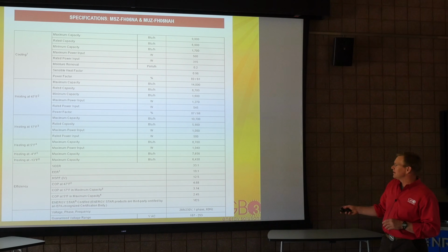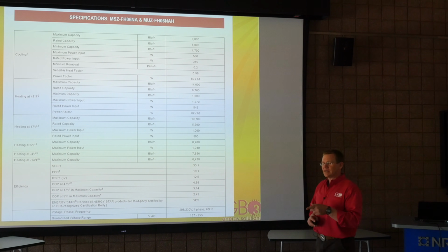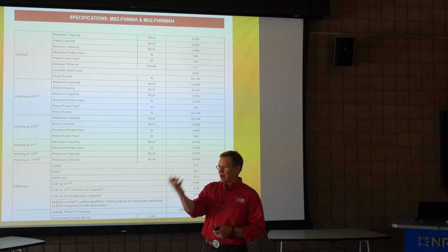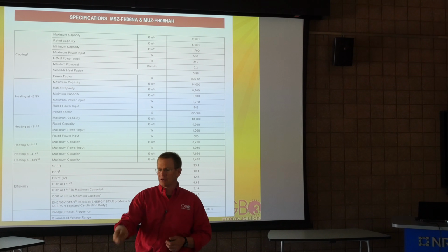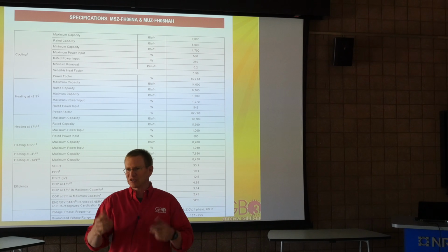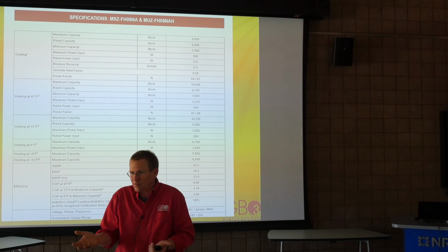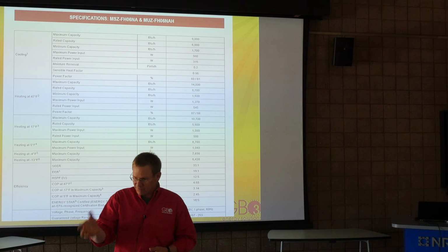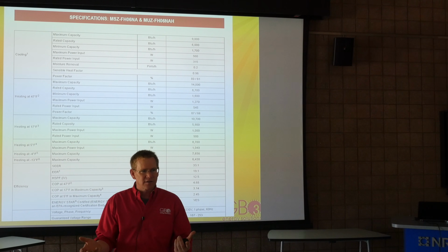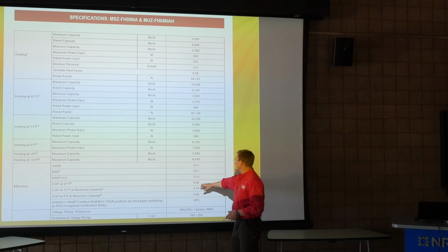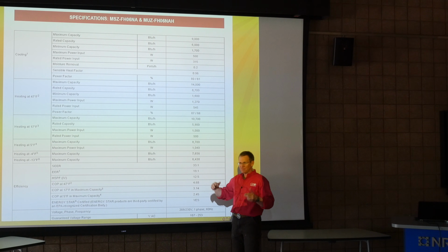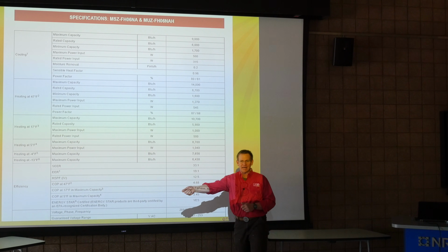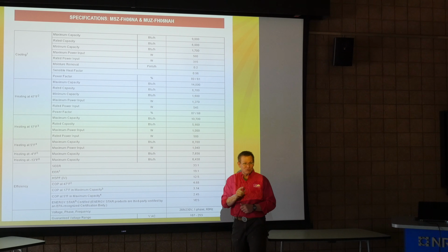So the COP, coefficient of performance - the best way to describe it is if you have a watt of power, it's equal to about 3.412 BTUs. So for every watt, if you put it through a resistive element, you get about 3 BTUs. Well, with heat pumps at a certain temperature, this is like getting 4.6 times 3 BTUs, so we'll call it 15 BTUs for every watt of power. So you can think of this as efficiency - this is 468% efficient. We're leveraging that electricity to make more heat than we would by just using the electricity directly. That's really cool, right?